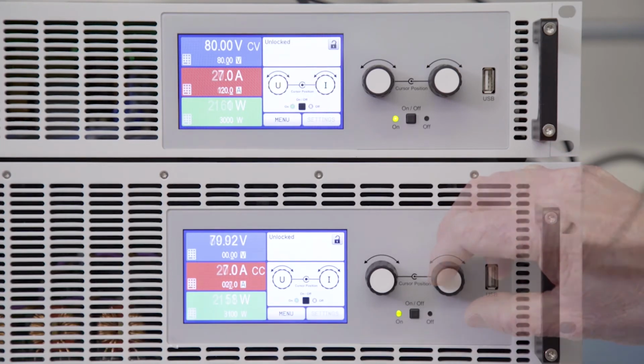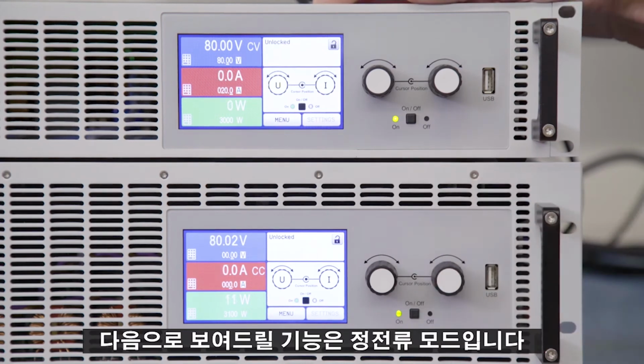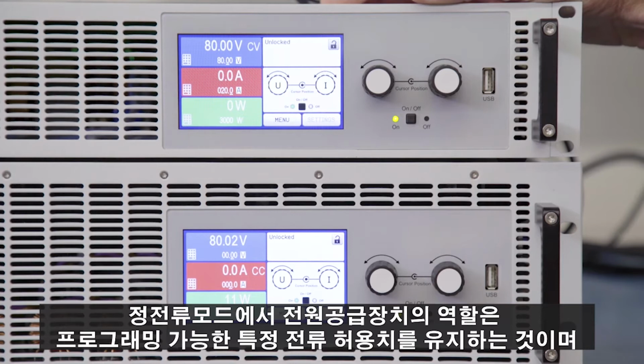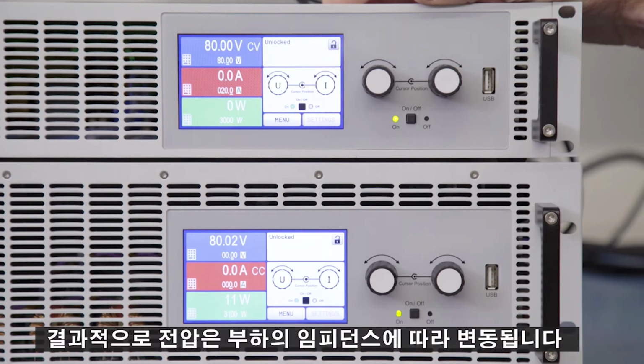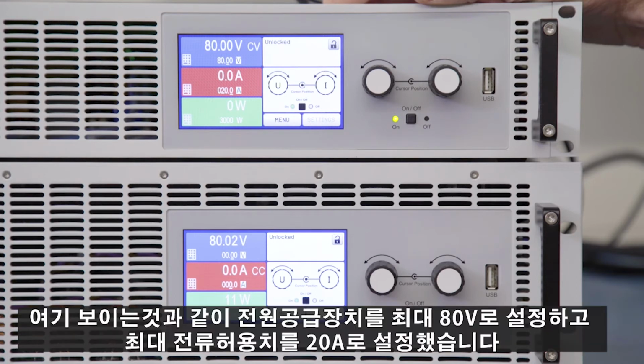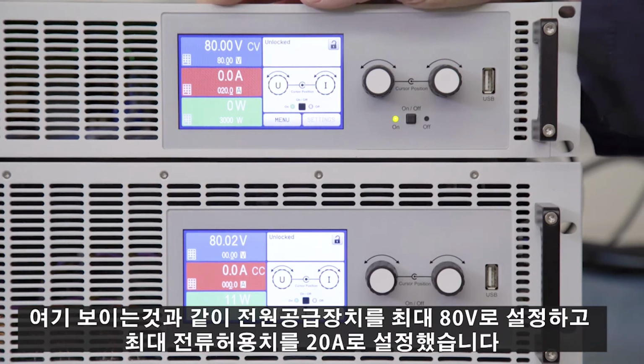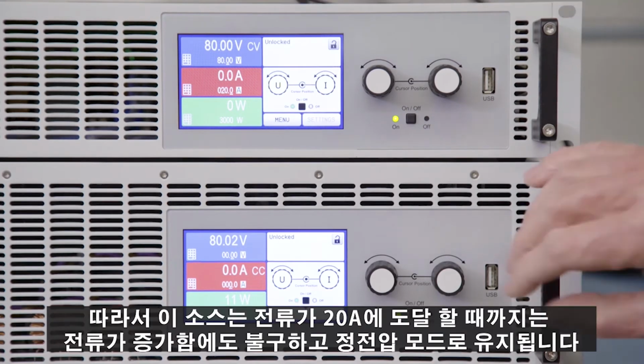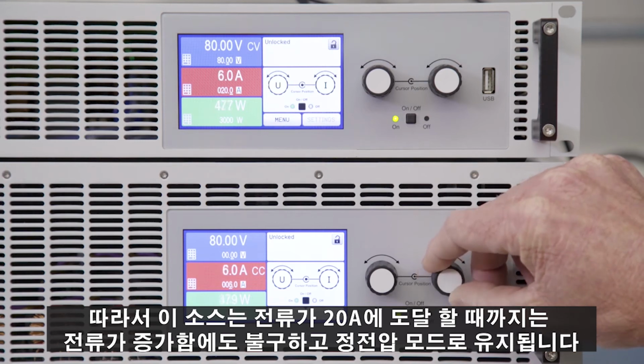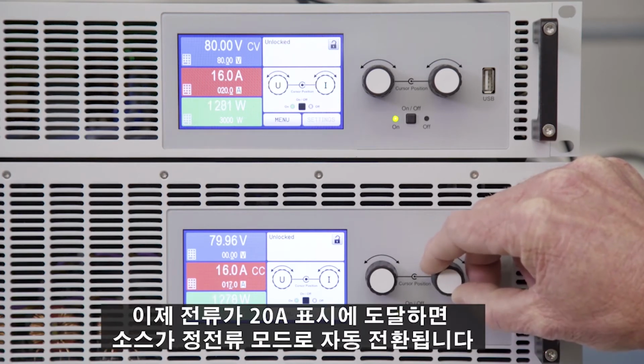This is probably the most common mode of operation for power supplies, but let's go ahead and take a look at constant current next. The second mode of operation that we're going to show is constant current. In constant current, the job of the power supply is to maintain a certain programmable current limit, and as a result, the voltage will then fluctuate according to the impedance of the load. Here, I've set the power supply up to 80 volts. I've also set it up to a maximum current limit of 20 amps. As I increase current, the source stays in constant voltage mode until I reach that 20 amp mark. Once I reach that 20 amp mark, the source is going to automatically switch over to constant current mode.